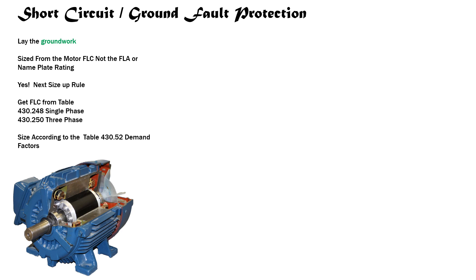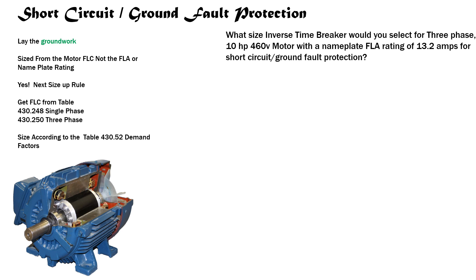I'm really excited about today's video. We're going to be bringing together everything that we've been learning this week and actually selecting our short circuit ground fault protection size. What size inverse time breaker would you select for a three-phase, 10 horsepower, 460 volt motor with a nameplate FLA rating of 13.2 amps for short circuit ground fault protection? Remember, when we're sizing short circuit ground fault protection, we're never going to use the FLA or the nameplate rating — we're only going to use the FLC.